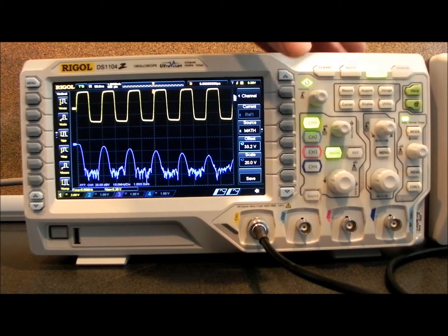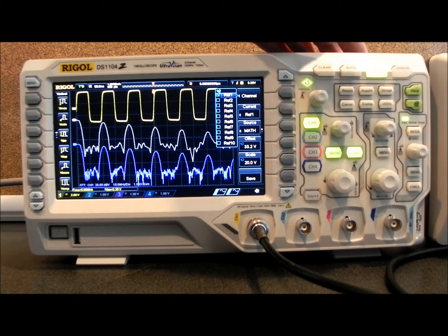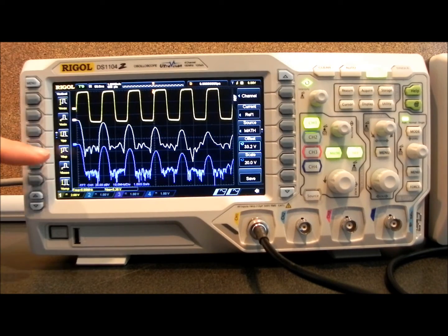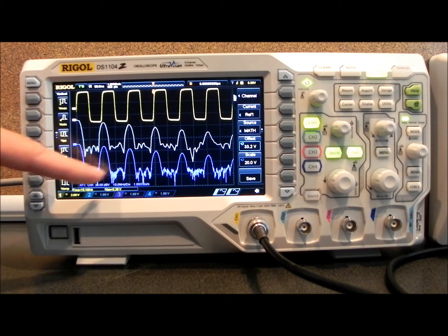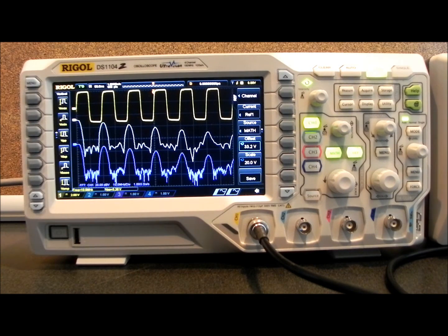I'm going to bring up the reference, which I saved earlier, and you can see the comparison between the high-resolution memory FFT, memory-based FFT, and the displayed-based FFT. It can be very useful if you need to have a higher resolution and be able to see smaller details of your FFT analysis.